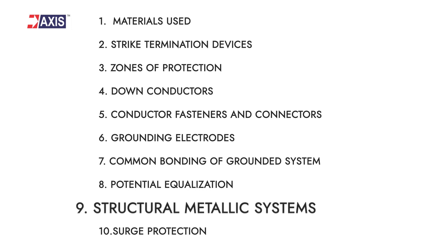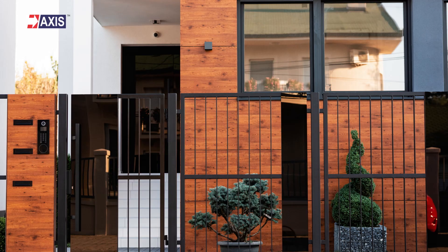Ninth: structural metallic systems. The metallic framework of the structure can be used as the main conductor of the lightning protection system, provided it offers a continuous path for current flow according to the methods specified in the standard. The strike termination devices must be connected to the metal framework using exterior conductors. The connections can be made by bonding, welding, brazing, drilling, and tapping. This framework is explained in depth in our video on how to select down conductors for lightning protection systems — the link is here and in the description.